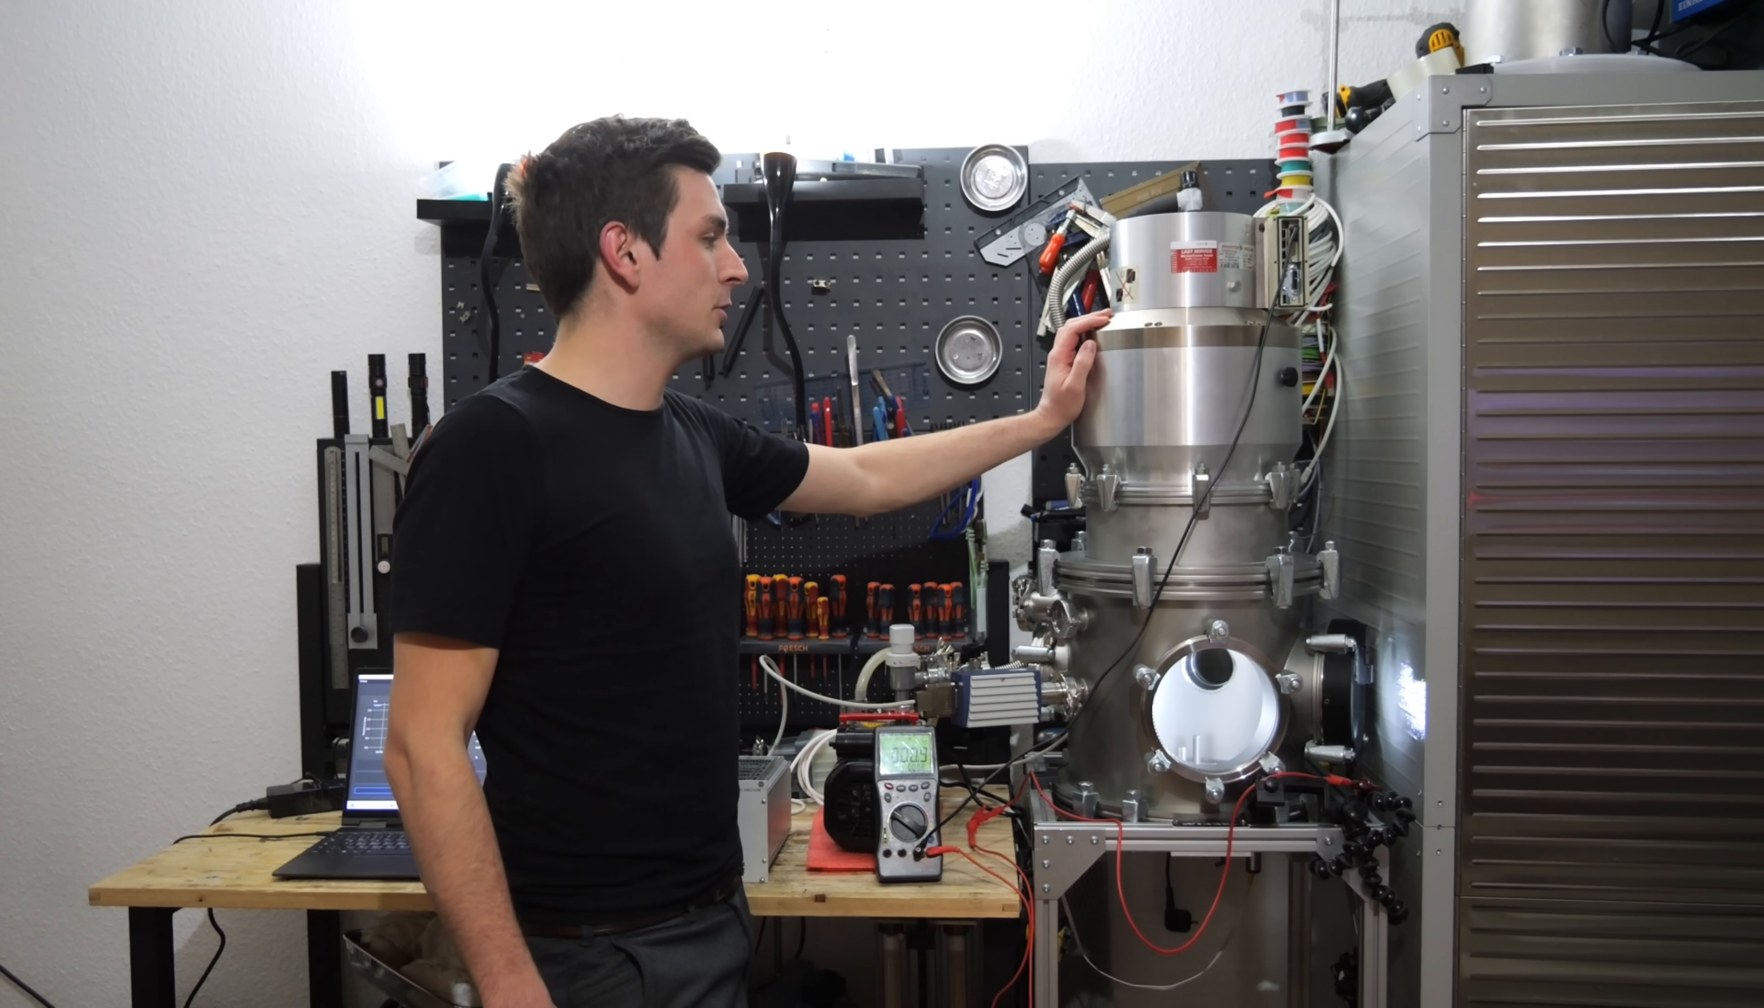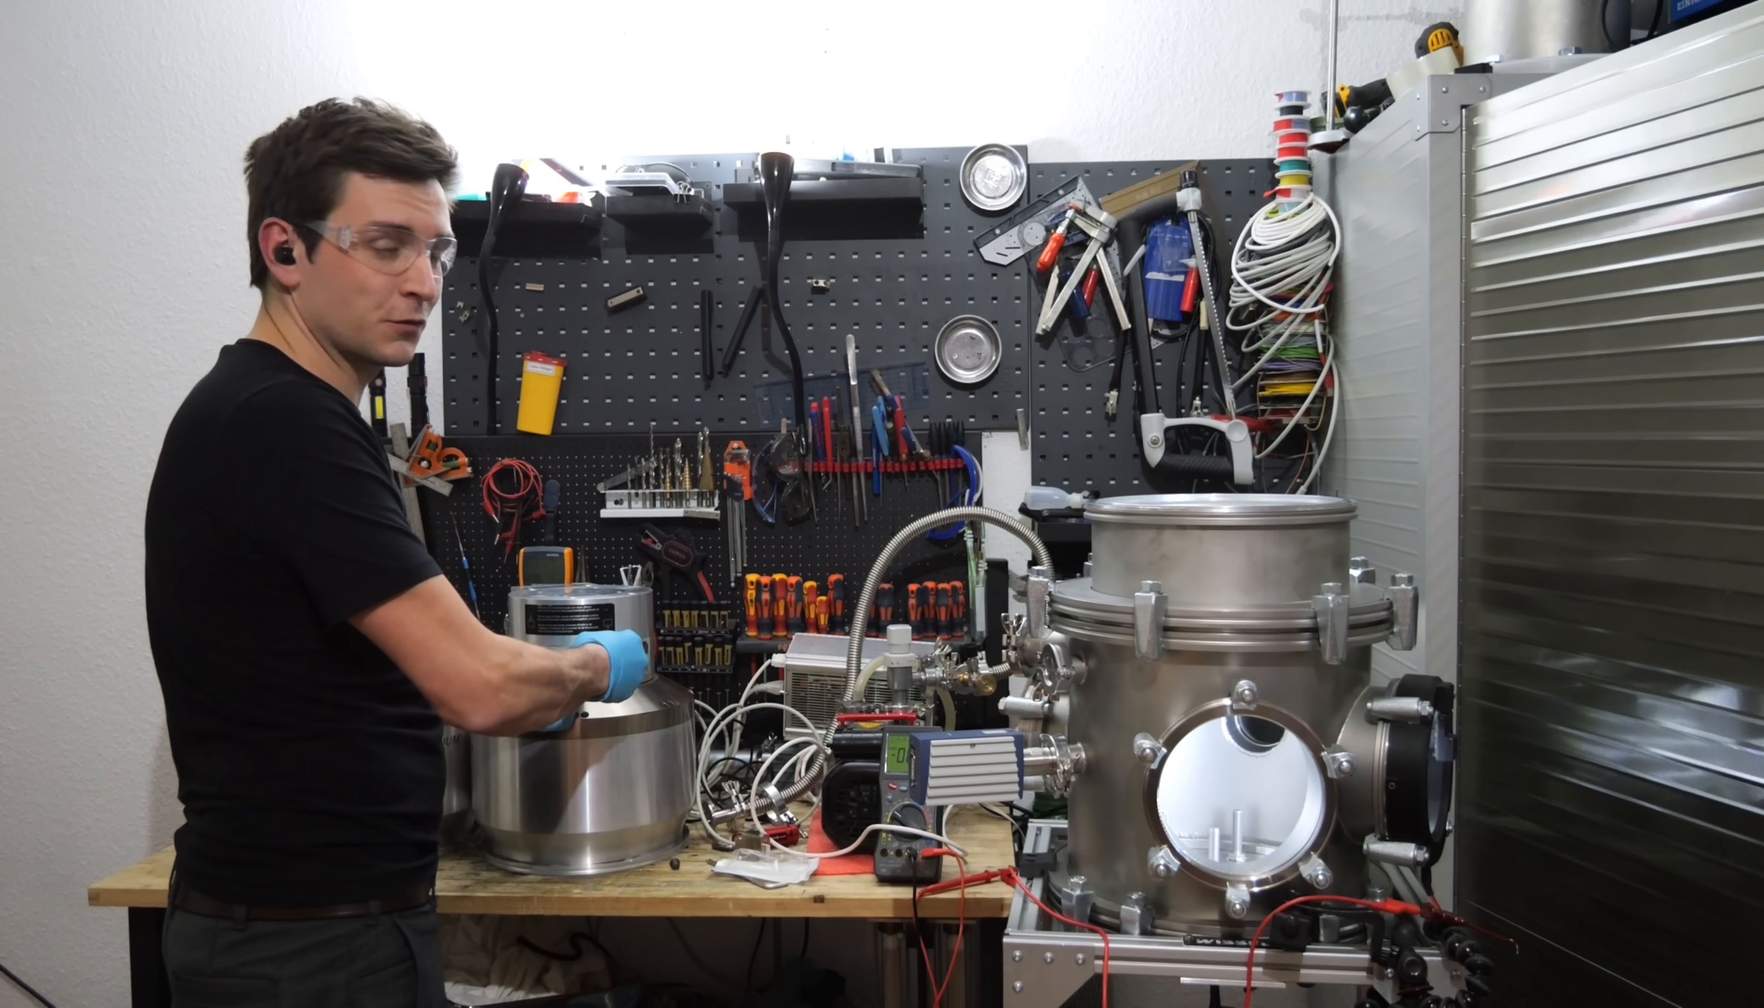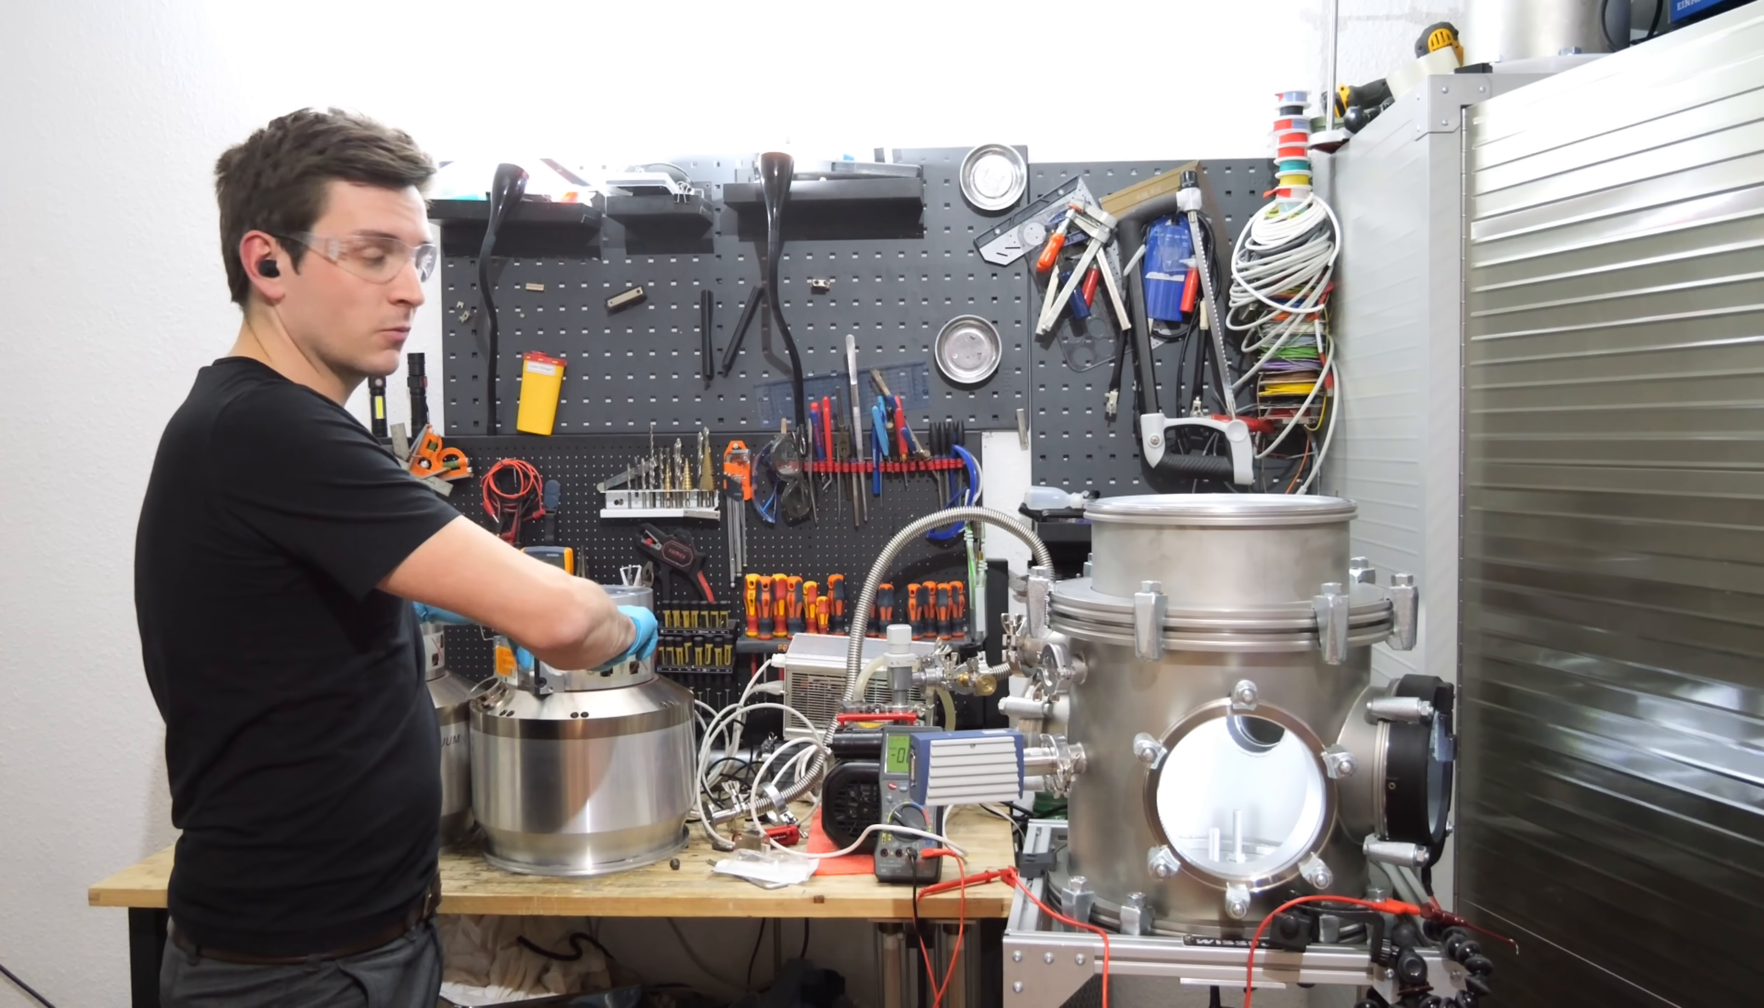But I think I will try to mount the pump I did not disassemble, fill in the oil I put into this pump into the other one. I am basically doing an oil transfusion. The oil is darn expensive and I only had enough oil for one pump, which is why I have to transfer it to the other one.